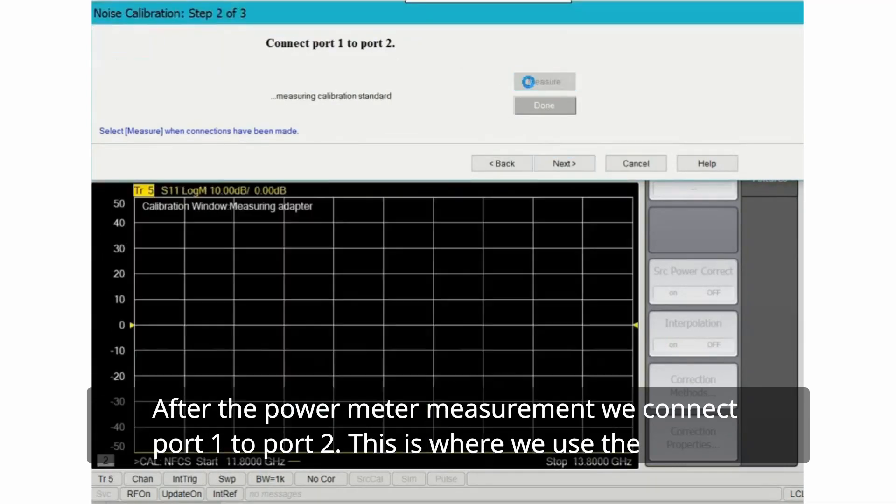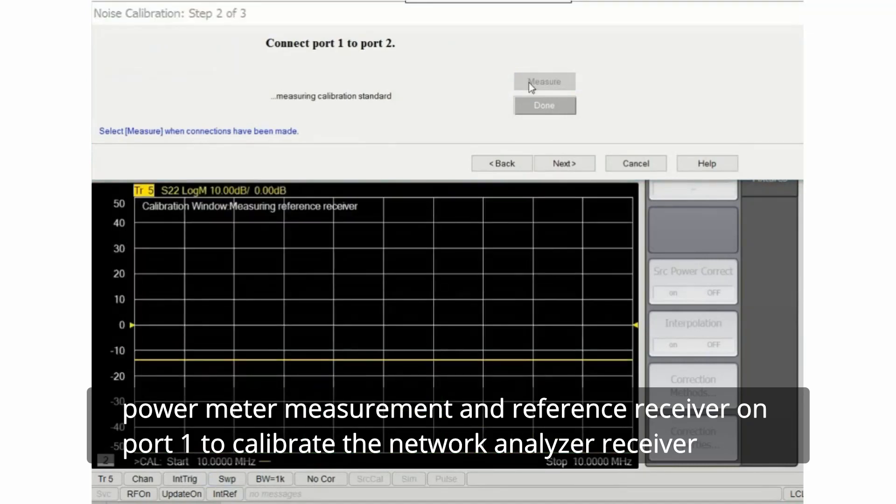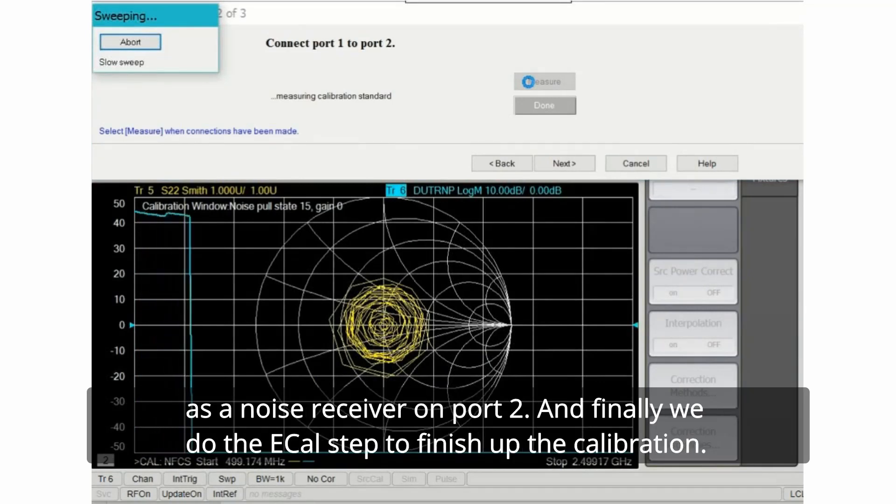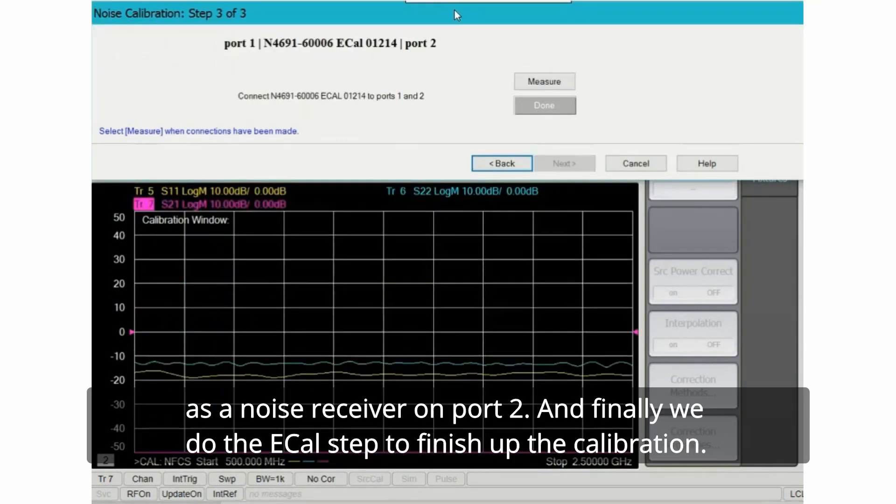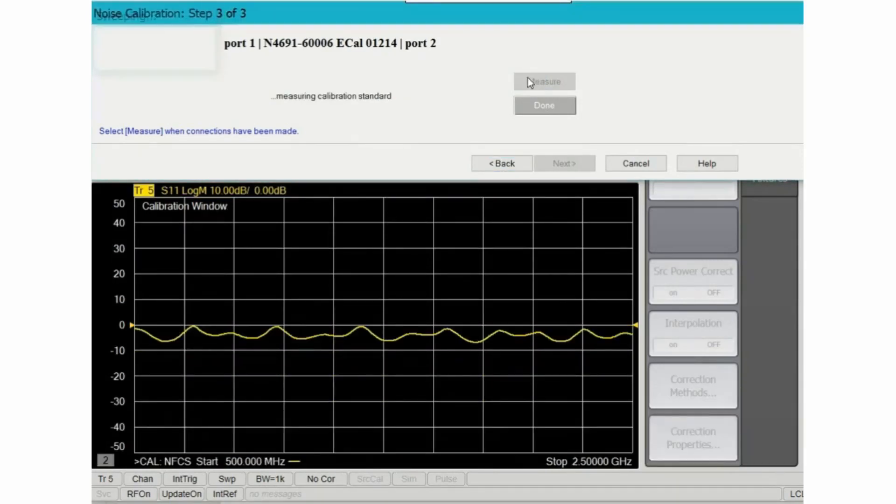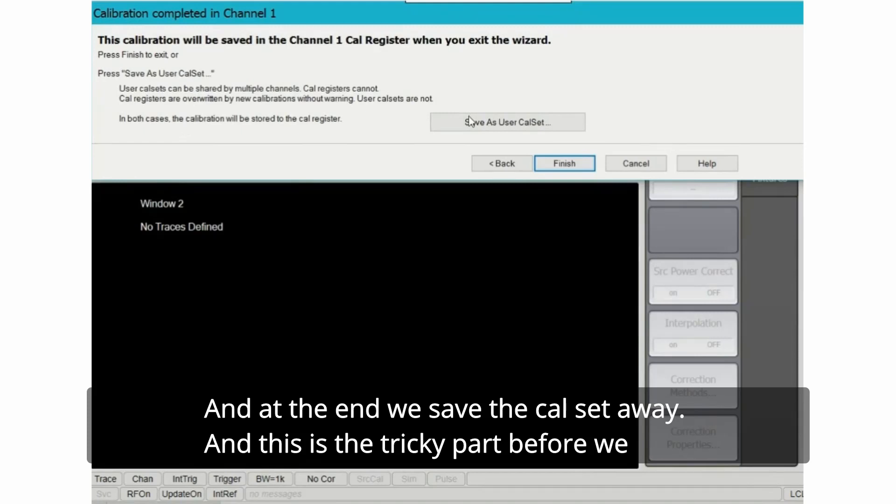After the power meter measurement, we connect port 1 to port 2. This is where we use the power meter measurement and a reference receiver on port 1 to calibrate the network analyzer receiver as a noise receiver on port 2. And finally we do the ECAL step to finish up the calibration.